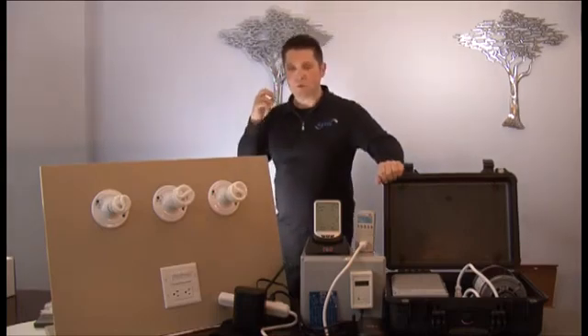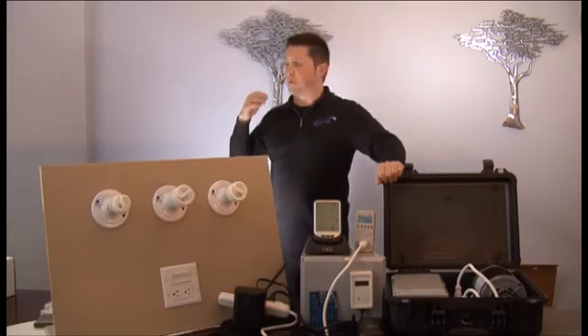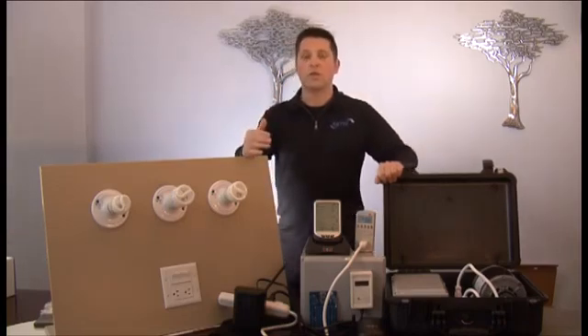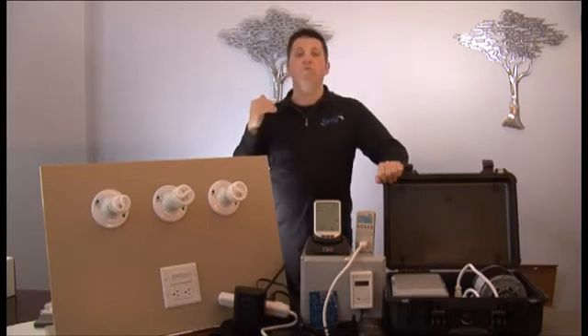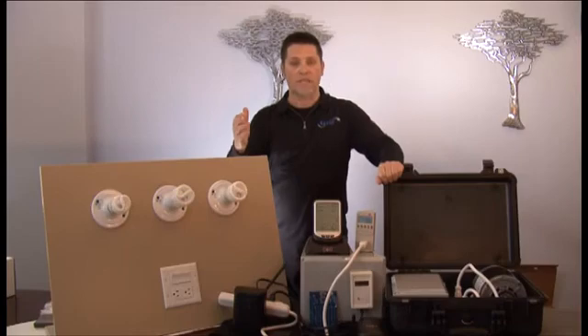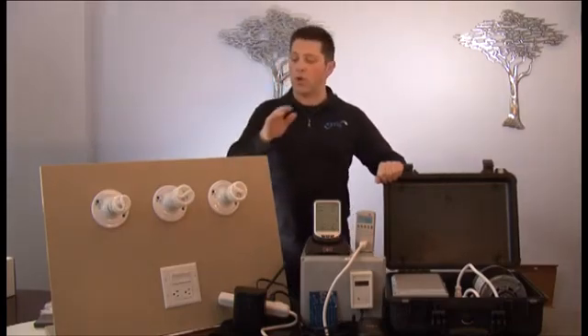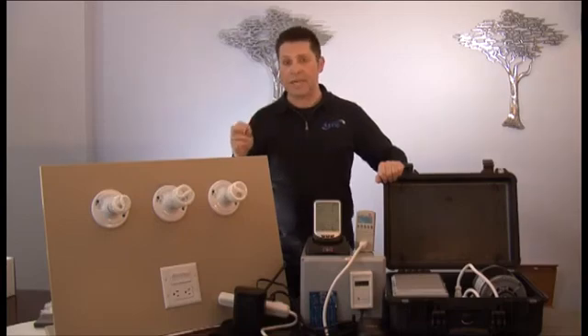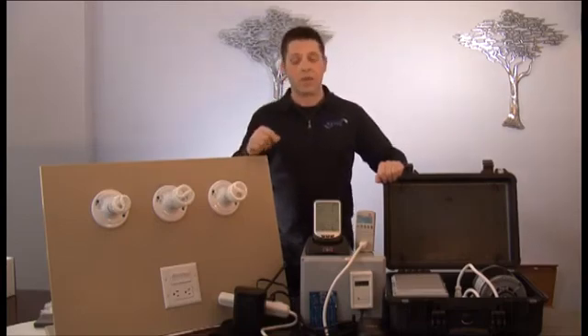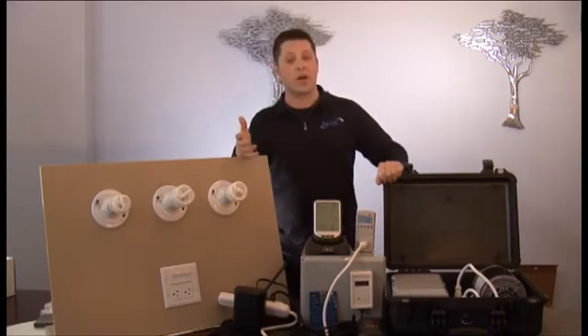Also, when you're moving this electricity from your substation or your distribution panel to your motors, out of phase, it's harder to push that electricity than it is in phase. So, for example, if you can make a motor run on less amps, you're almost guaranteed to have less heat, both in the motor and in the line, and save some money. There are other places where this will save money on the inrush.